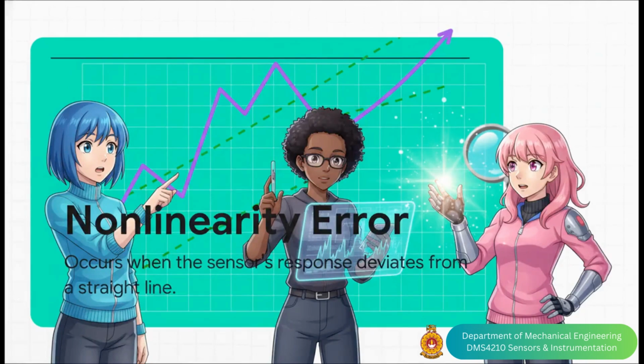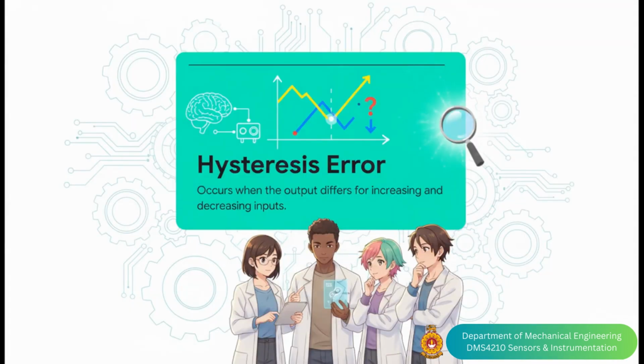Then there's nonlinearity. This is when the sensor's response isn't a straight line at all, it's curvy. It might be accurate at low temperatures, way off in the middle, and then sort of accurate again at high temperatures. It's an unpredictable error that changes all over the place. And finally, one of my favorites, hysteresis. This one is really fascinating. It's like the sensor has a memory. It gives you one reading when the temperature is rising, but a totally different reading for the exact same temperature when it's falling.